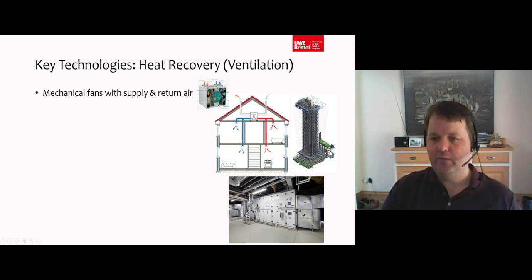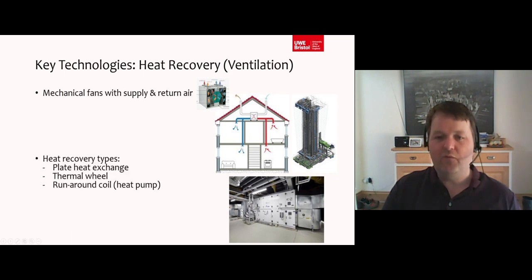There's a technique for doing that as well. Then the return air comes back on a separate set of ductwork. Again, that's very common in commercial buildings like this, a complete second set of ductwork coming back up to the air handler units. So you can see there, one would be a supply going out, the other would be the return coming back. You do some form of heat recovery then.